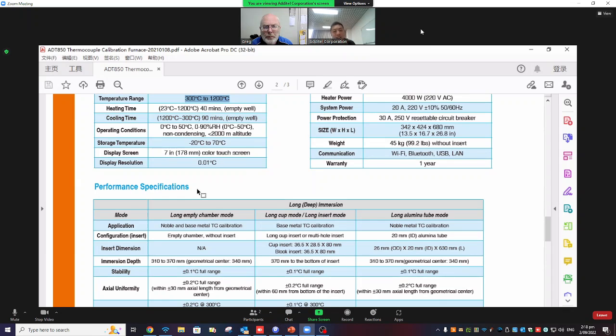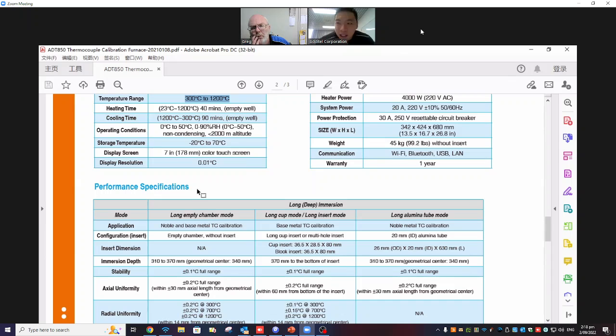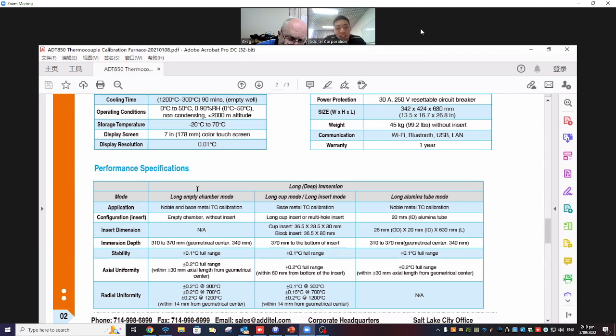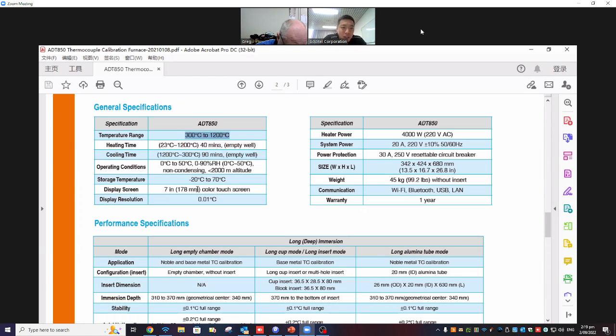The reason why we do that is because the heating components have limited performance at high temperature. If you look at our competitors, they have the same thing, 300 to 1200. They don't give this specification below 300 degrees Celsius because the heating wire is unstable there. This is all because the heating wire has pretty high resistance, and below 300 degrees Celsius the supply is not that stable. So we may have pretty bad stability or uniformity, but this is common with other competitors, so we actually don't need to worry about that.